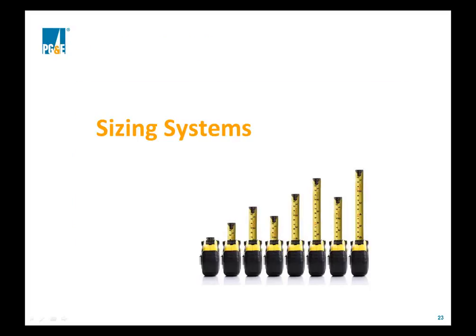So there are some sizing guidelines that we provide. They're based on some general solar thermal rules of thumb. Some of them are there to prevent things like unnecessary oversizing of systems. One thing to keep in mind with solar thermal is, unlike PV, which can be interconnected to the grid, solar thermal is standalone and is really dependent on the solar storage tank being sufficiently sized to store all of the hot water that will be generated by the system in a day, and also on not having an excessive amount of collector area based on the amount of hot water that the facility uses in a day. So next slide.